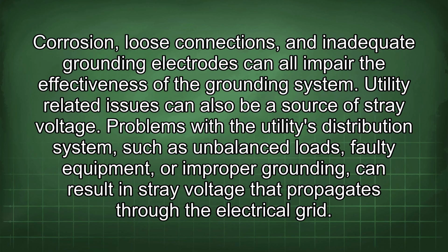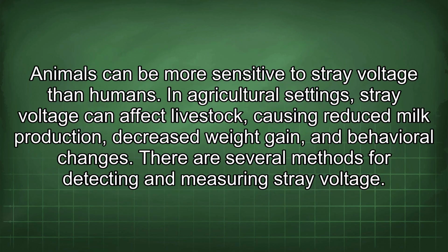Utility-related issues can also be a source of stray voltage. Problems with the utility's distribution system, such as imbalanced loads, faulty equipment, or improper grounding, can result in stray voltage that propagates through the electrical grid. Animals can be more sensitive to stray voltage than humans. In agricultural settings, stray voltage can affect livestock, causing reduced milk production, decreased weight gain, and behavioral changes.